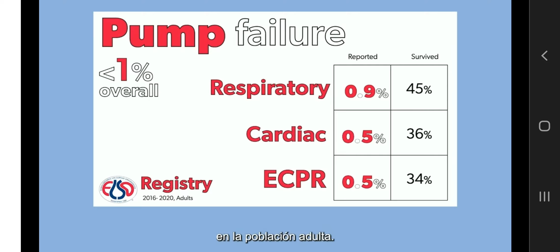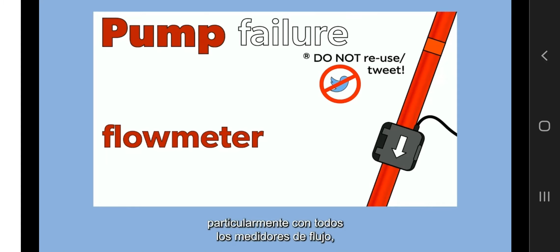even if pump failure is not so frequently reported in the adult population. But when your blood flow stops, also exclude a failing flow sensor, meaning a flow sensor no longer able to properly read blood flow, but with the pump properly running. Circuit pressures will be preserved and hemodynamics and gas exchange will not be impaired.